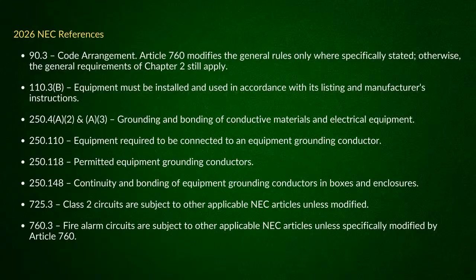Well, you got to remember, just take like a receptacle or switch, and you jumper everything and bond everything in. Why do you do that? Because you have metal on that switch. But these little devices, the covers are non-metallic, the switch is non-metallic. When you disconnect it, you don't have that exposure at that point. So I would make the argument in this case that that wire mold is not continuous and listed for grounding.